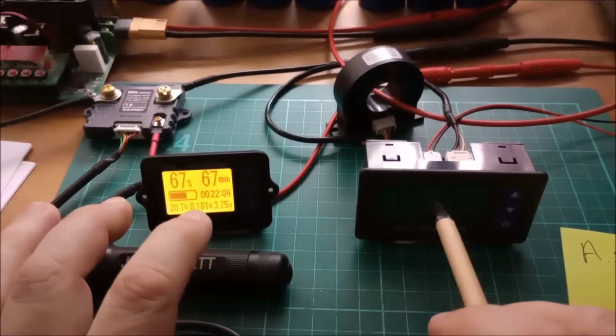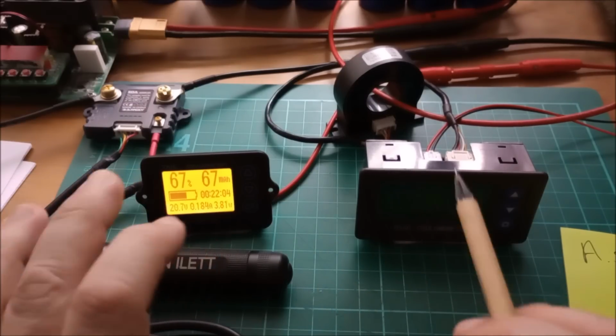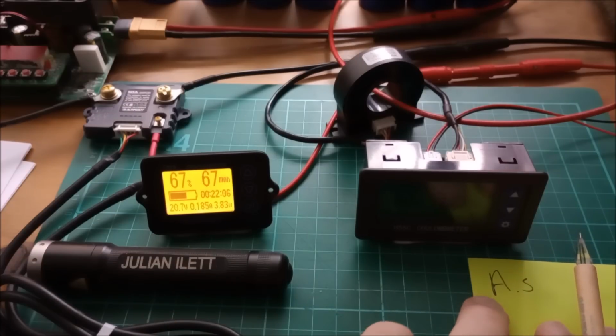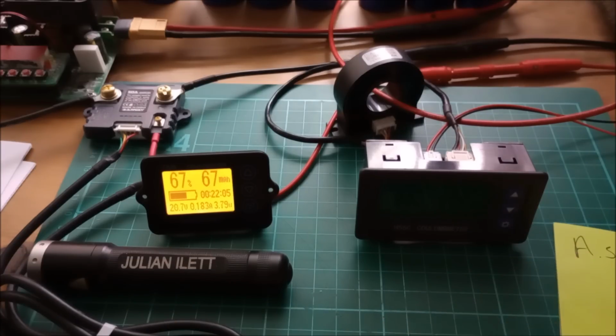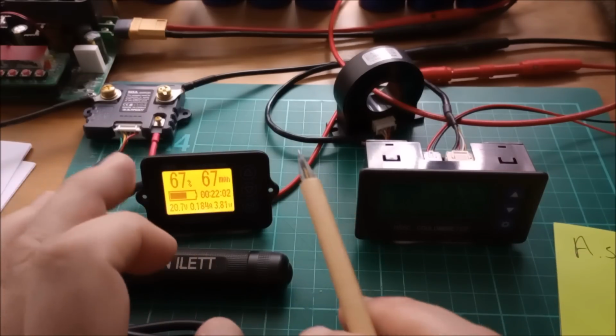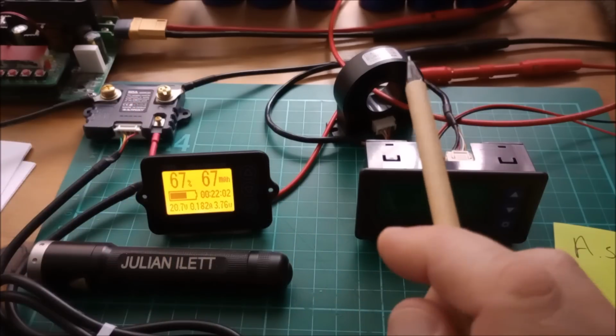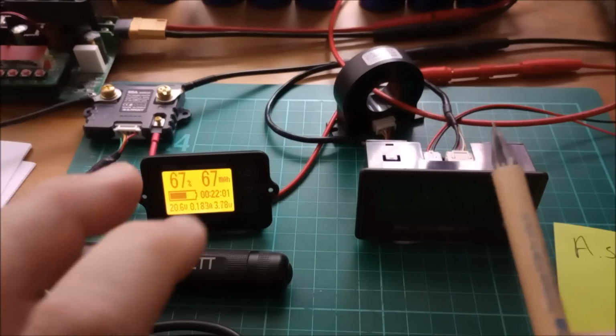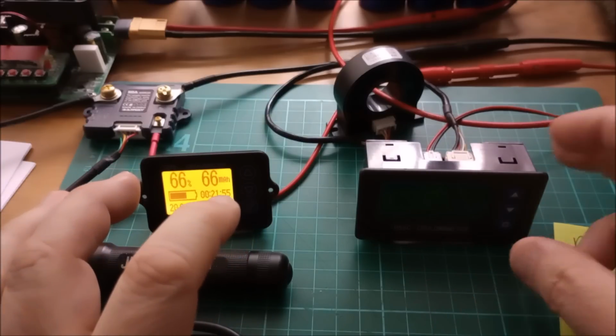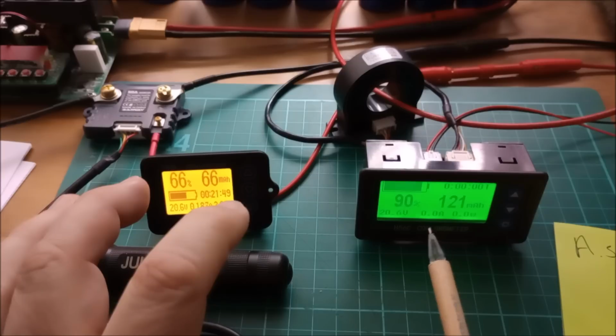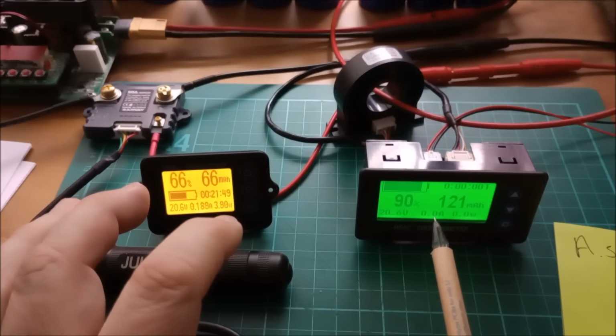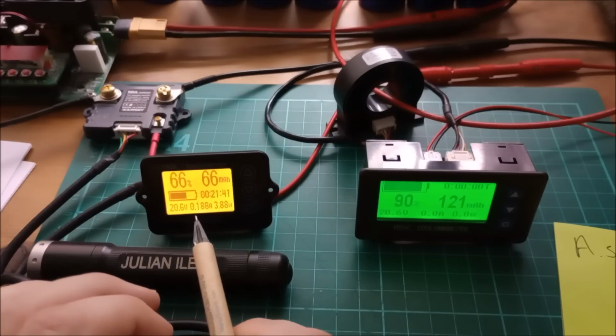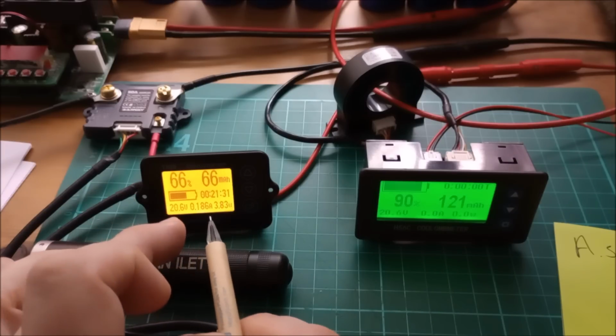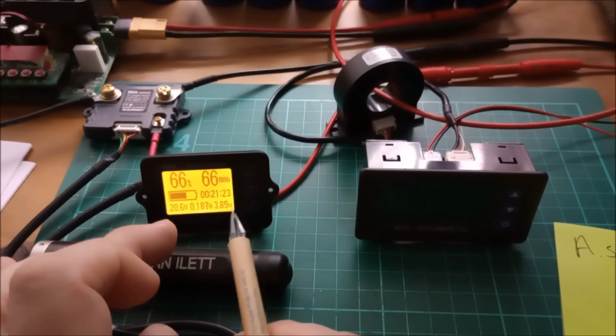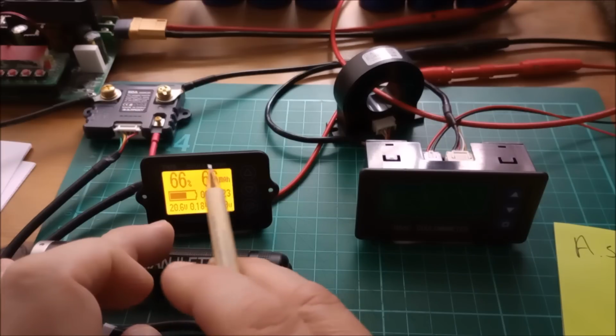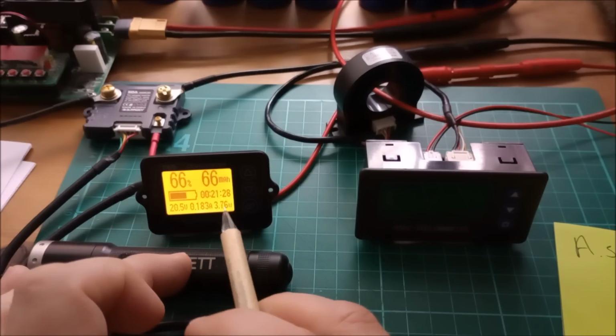The way these things work is they're measuring amps and counting seconds, so they are measuring amp seconds. Every amp second that flows through either this current shunt or this current transformer is counted and registered by these units. This one isn't counting at the moment because I'm below the minimum threshold current. This one is counting because it has a better current threshold - anything above 50 milliamps, I think it counts - and it's continuing to count down.